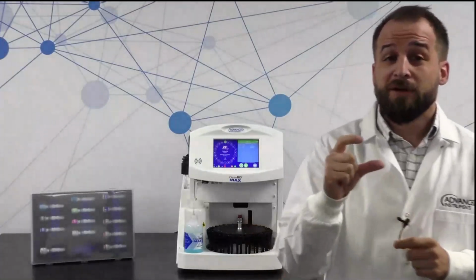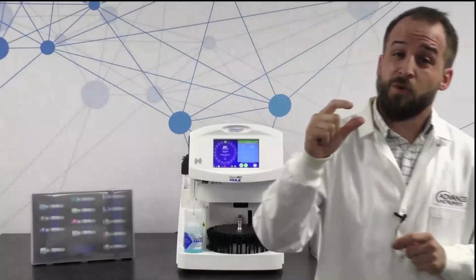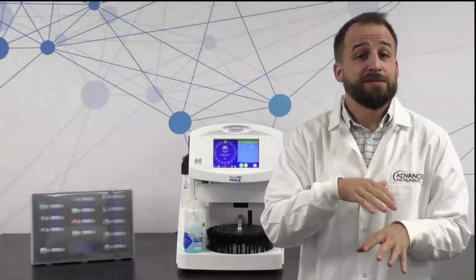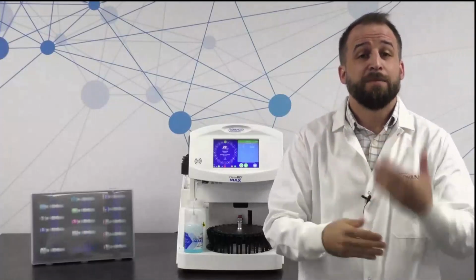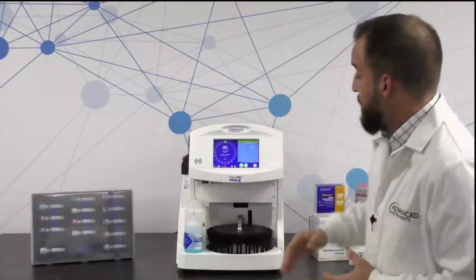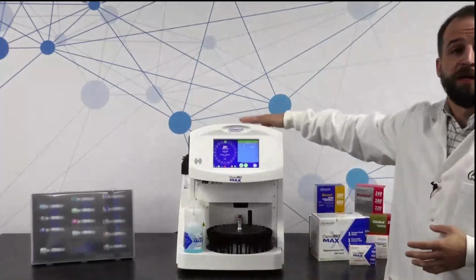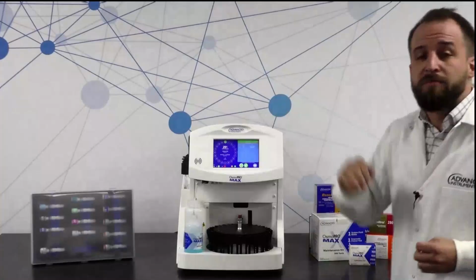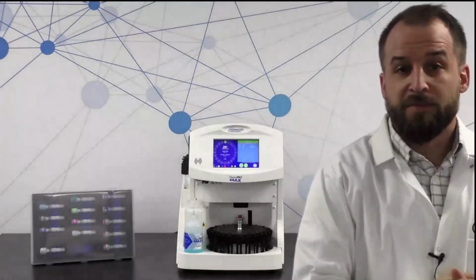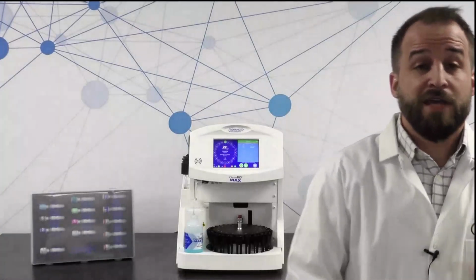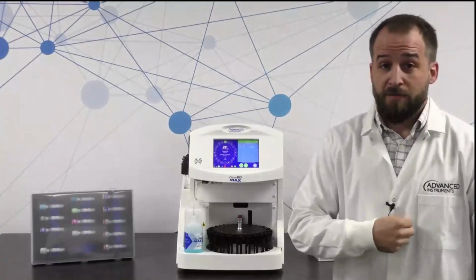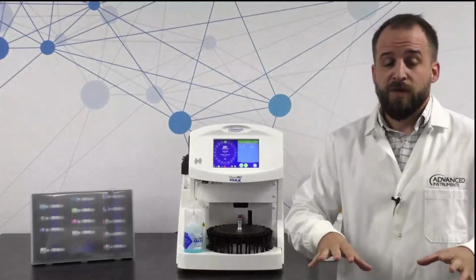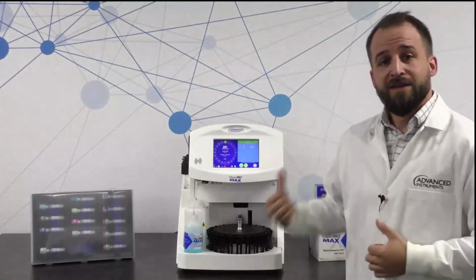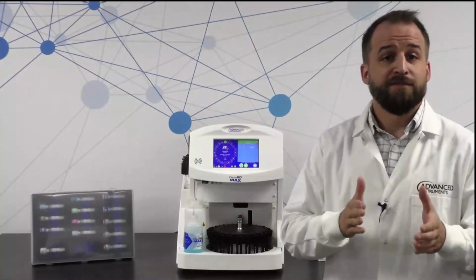And out of that primary sample tube, you're going to need at least 480 microliters, but it's only going to aspirate 190 microliters, to accommodate for that dead volume, so that the liquid level sense technology can do what it does and make sure that it's properly aspirating sample from your primary sample tubes without doing things like running into gels or bumping into the bottom of the tube. So it's super important that we accommodate for that dead volume so that the instrument can do its thing, so you don't have to pipette.